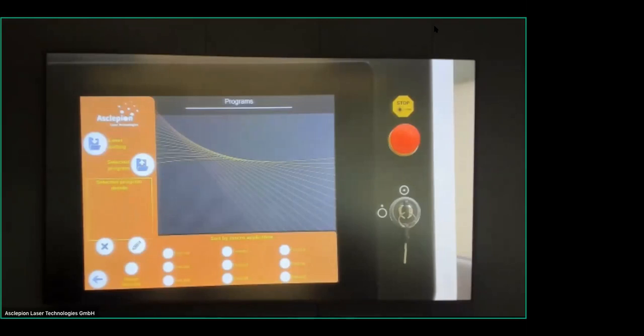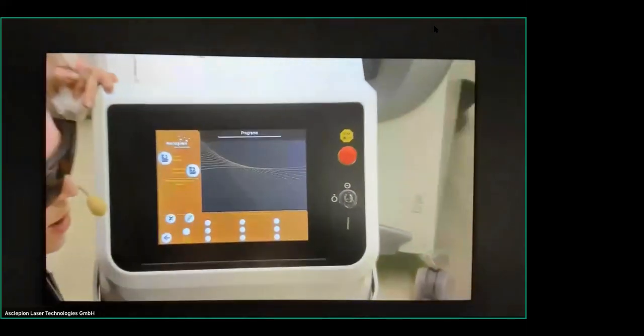So to be very precise here, you don't have pre-settings, because it doesn't make any sense to have pre-settings in a tattoo removal station. As you might know, and we were talking about that, we need to have a good clinical endpoint, and this is the point where I decide whether I increase or decrease the energy. So it's my clinical endpoint that makes the difference here. Most of the time, I'm choosing the parameters because of my experience and not because of the database.